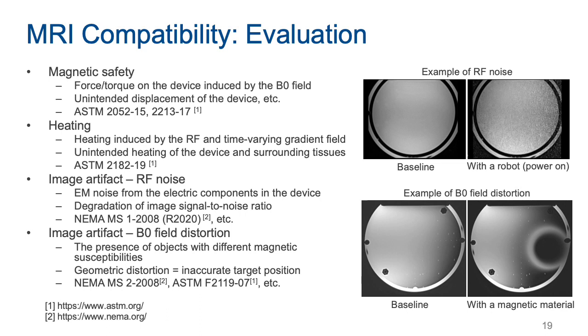Testing of the device is crucial to ensure MRI compatibility. Magnetic safety can be tested with ASTM standard 2052-15 and 2213-17. These tests allow quantifying the force and torque on the device in the MRI environment. Another ASTM standard, 2182-19, is designed to quantify the heating of the device induced by the RF and gradient field. There are also standards to test image artifacts due to RF noise and B0 field distortions. NEMA MS1 2008 is used to quantify the EM noise on the MR image, whereas NEMA MS2 2008 and ASTM 2119-07 are used to quantify geometric distortion of the image due to the presence of objects with different magnetic susceptibilities.